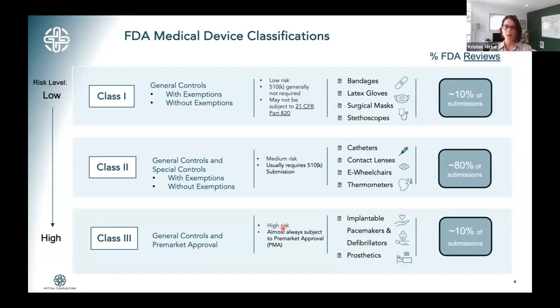After that, you would want to have a regulatory person step in and really do a deep dive to see which class and which regulatory pathway are appropriate. This is because devices are so different from each other, depending on where they are in the body or what the indications for use are, they have very different risk levels and potential intended purposes. So many devices on the surface may look like they belong in one class, but depending on how specific you want your indications for use to be, that can actually change which class and which submission pathway you need to go through with the FDA.